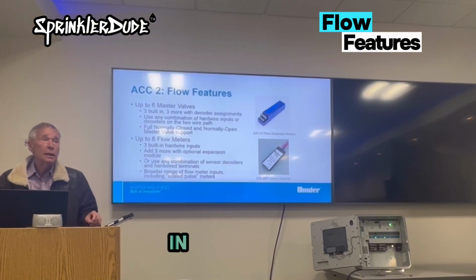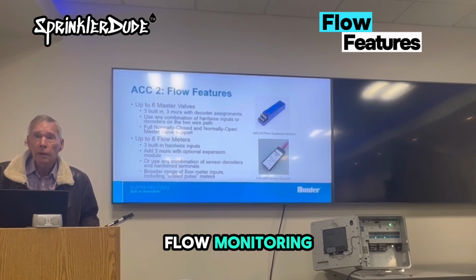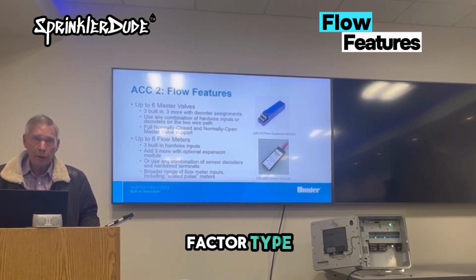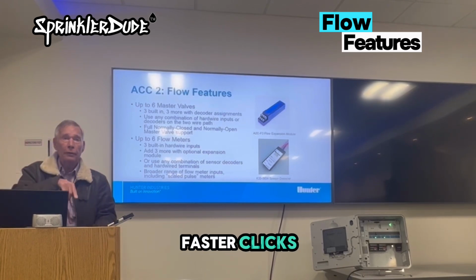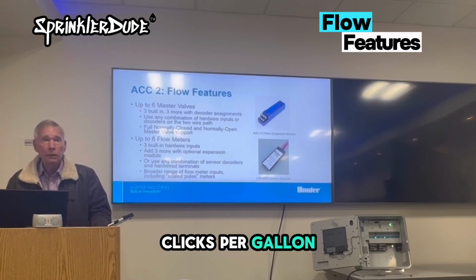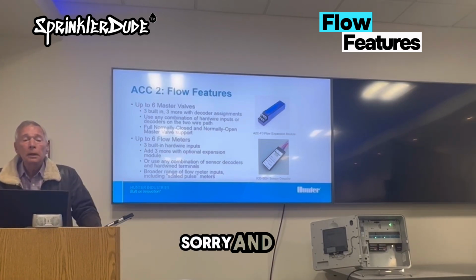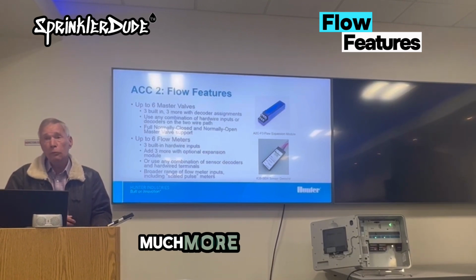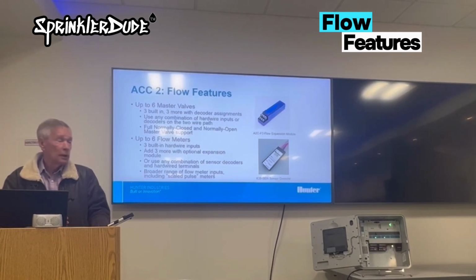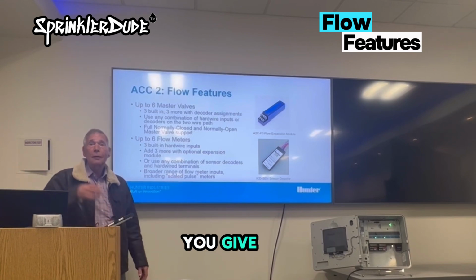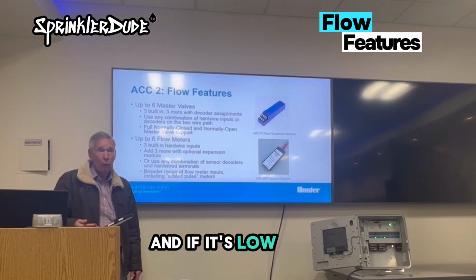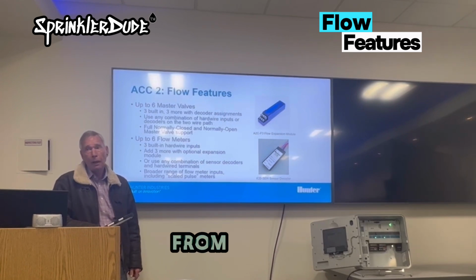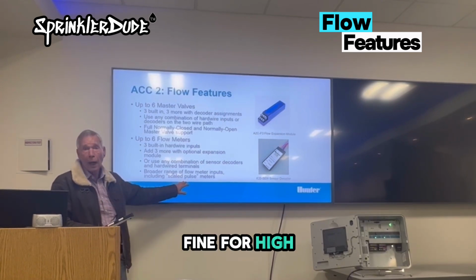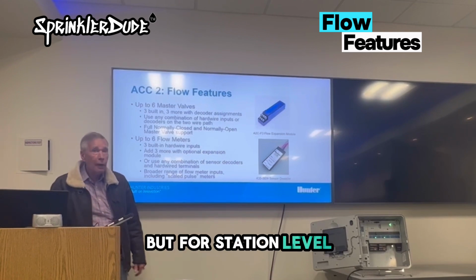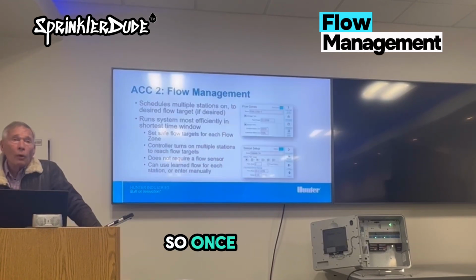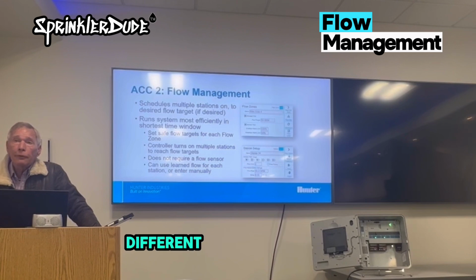If you're interested in station level flow monitoring, we prefer the K factor type because we get way faster clicks. We get more clicks per gallon, or per liter, sorry. And so it lets us do diagnostics much more accurately and much faster. These scaled pulse meters, you get 1 click per gallon, and if it's low flow, you get very little feedback from the field. So they work fine for high flow shutdowns, but for station level diagnostics, not as good.